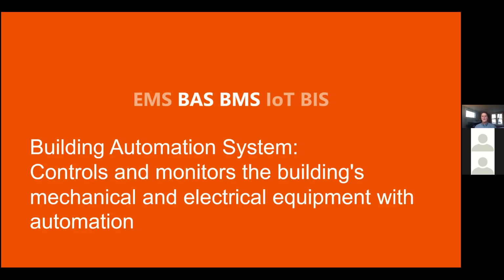If you have a simple building that really just has single or dual set point devices, like rooftop units or heat pumps, an EMS can do most of what you want. But as soon as you get into a building with any kind of zoning or a central plant, you have to have a BMS to help institute the sequences of operation that are needed, like a VAV, the most common type of zoning system, or even a hydronic building with water source heat pumps or 2 or 4 pipe fan coils. Even though each of those terminal units is single or dual set point, they do require hot and chill water from a central plant.